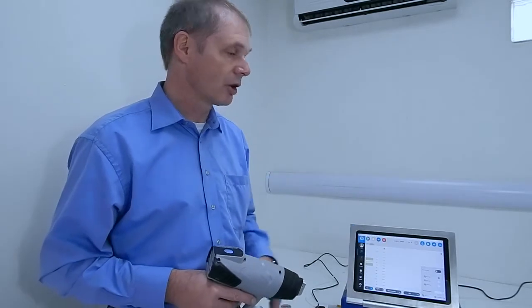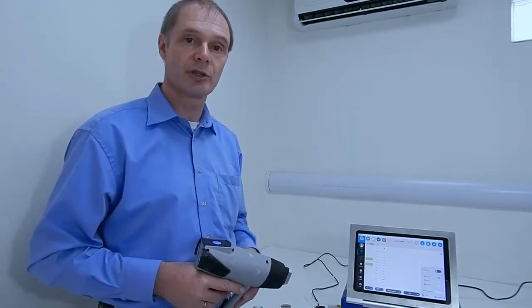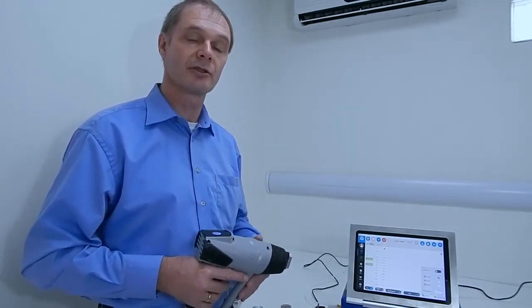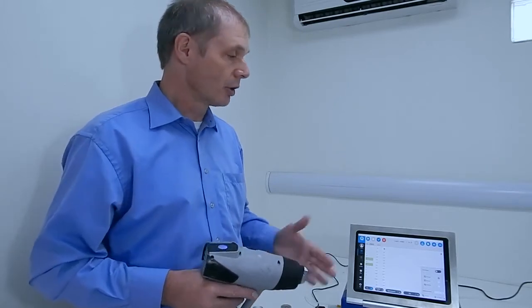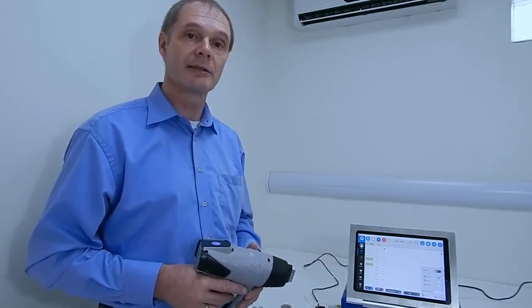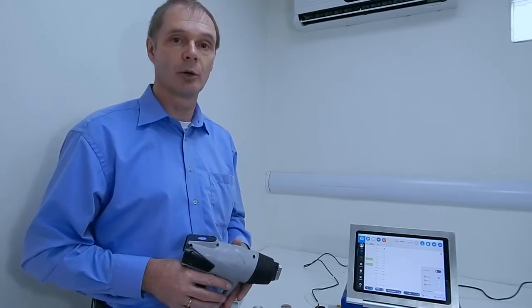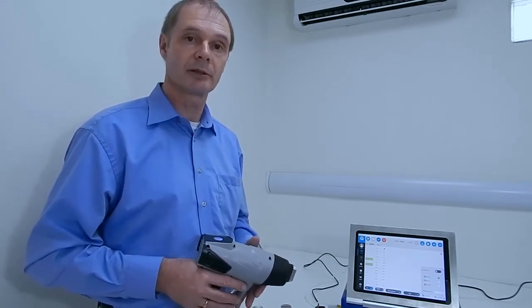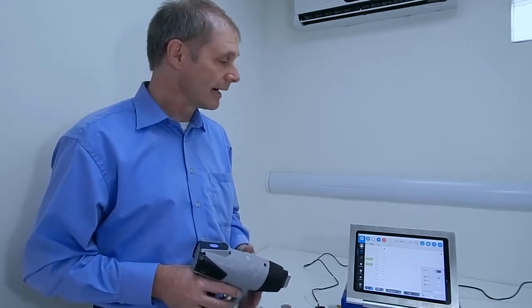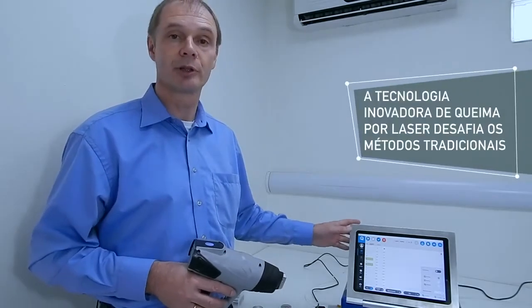Then we also have an economy mode, which automatically switches off the argon consumption whenever the instrument is in idle. So all in all, your argon consumption is at least 80% lower than with a conventional spark spectrometer. And it remains a portable solution even if you have argon on board.